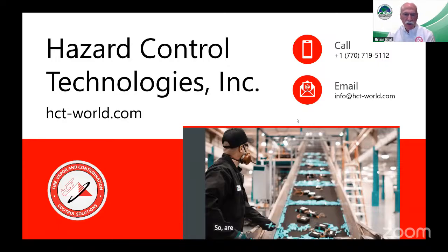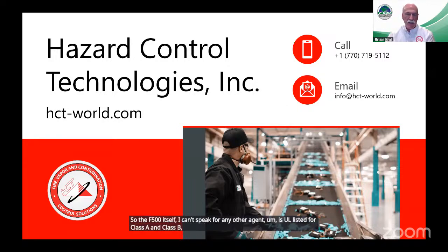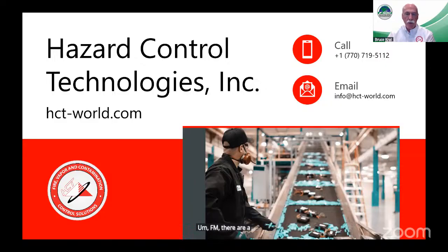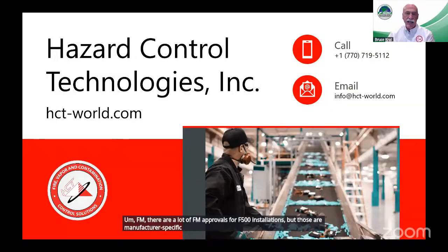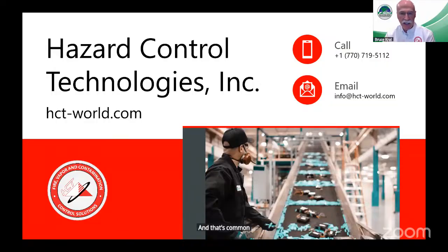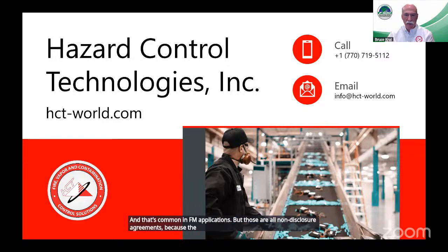So are there any specific listing or approval agent for UL or FM? The F500 itself, I can't speak for any other agent, is UL listed for Class A and Class B. And right now, UL considers a battery Class A since there's no other classification. FM, there are a lot of FM approvals for F500 installations, but those are manufacturer specific, where we worked with FM in testing a solution that the manufacturer wanted to use. And that's common in FM applications. But those are all non-disclosure agreements because the manufacturers don't want to give away their protection secrets.